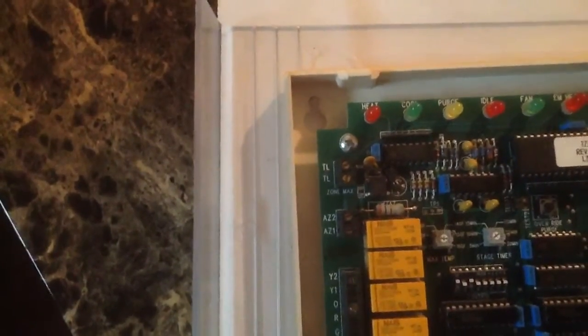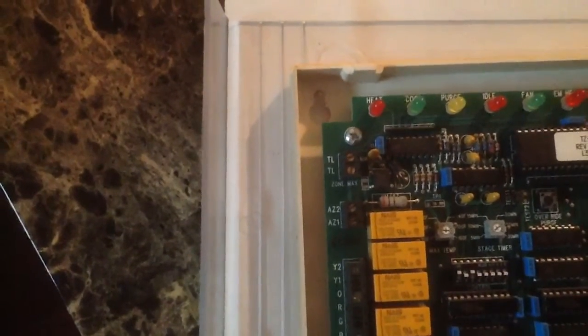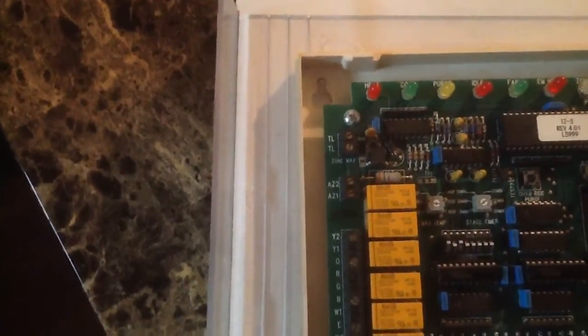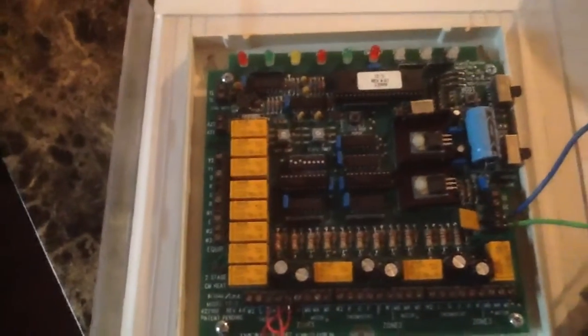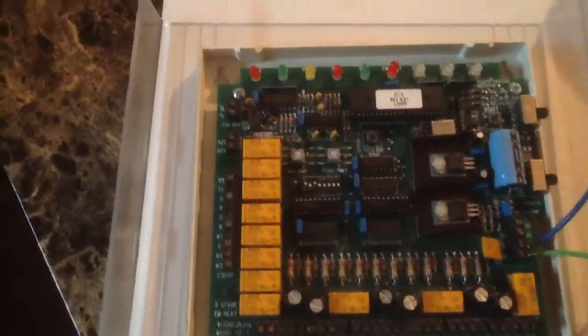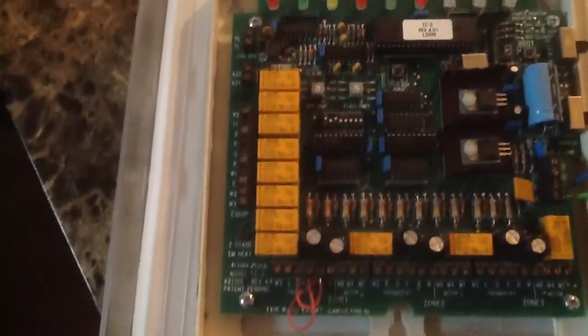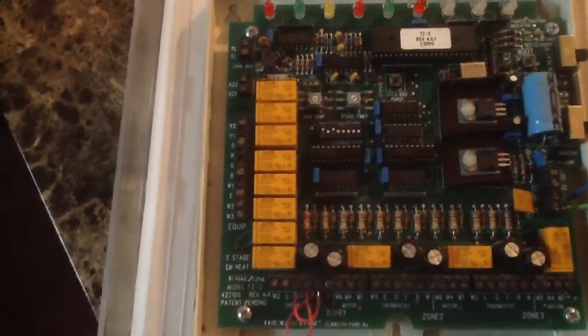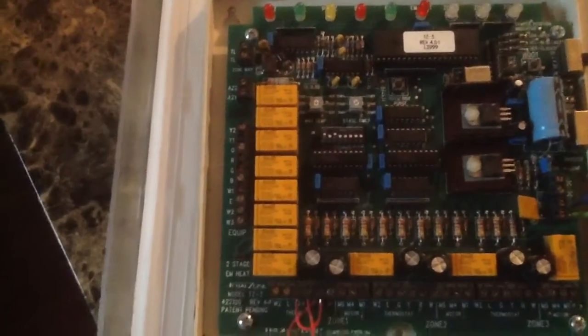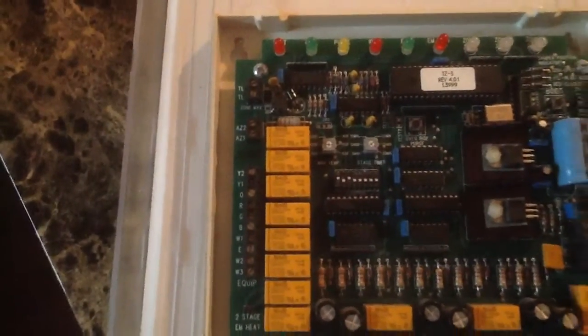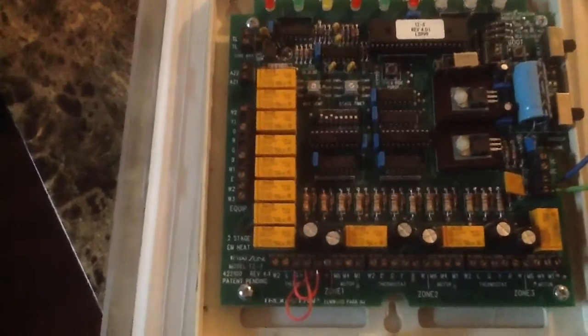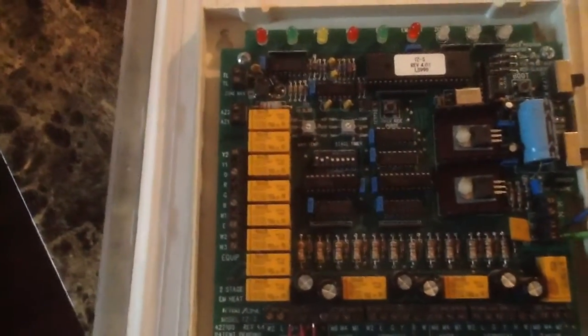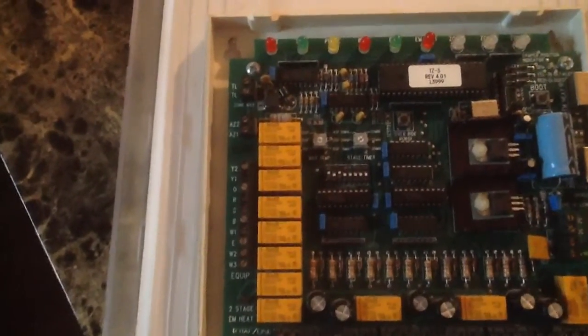And then the two TL terminals over here on the top left side of the board, that's going to be for your temperature, your discharge air sensor. This one actually didn't have one, which I'm not surprised. Most people end up not putting sensors in there. I don't know why. The system works way more efficiently and safely with them. That's what they're there for. EWC actually sends a supply air sensor with all their zone boards, so you don't have to worry about ordering one additionally.